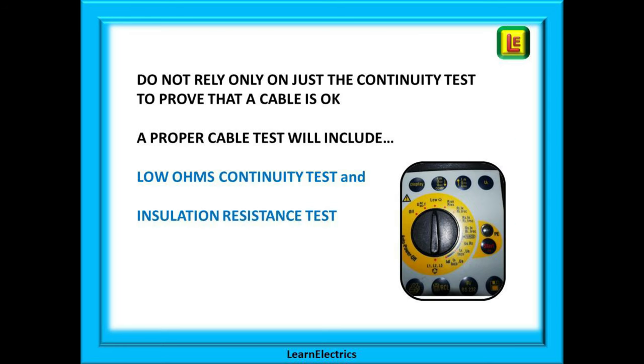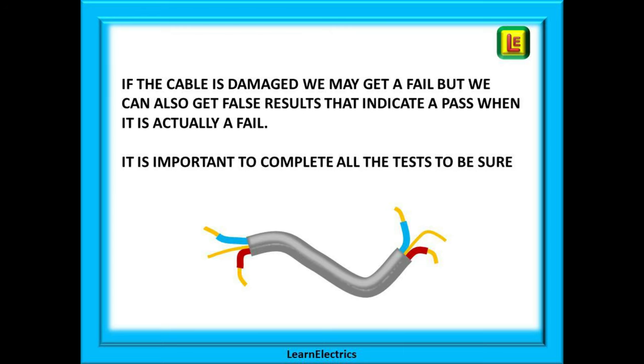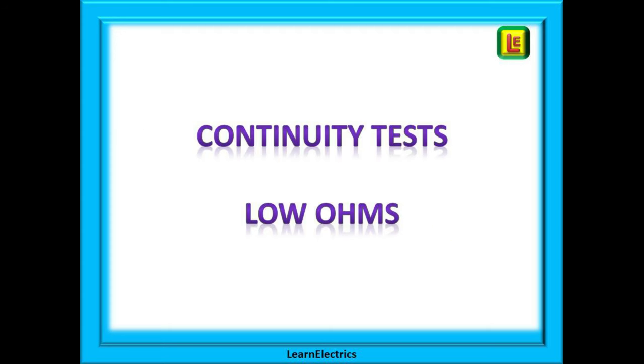We should not rely on just one test — the continuity test — to declare that a cable is okay. A full set of tests will include the low ohms continuity test and the insulation resistance test. If the cable is damaged we may get a fail, but we can also get false results — perhaps double fails that indicate a pass when it is actually a fail. It is important to complete all the tests to be sure the cable is in fact okay, and we should always begin with the continuity or low ohms test.